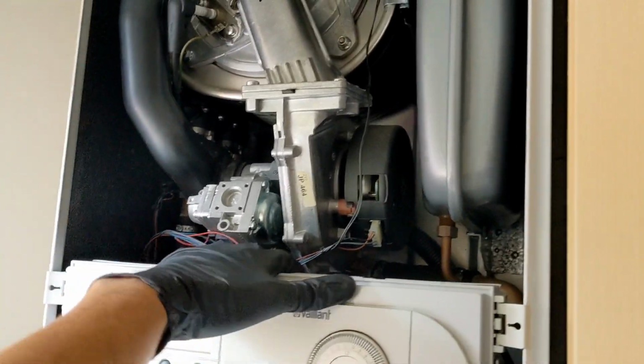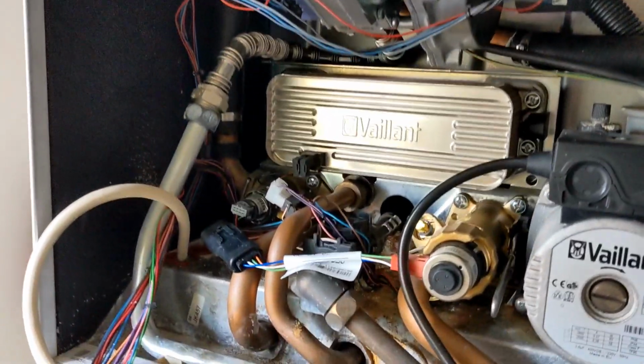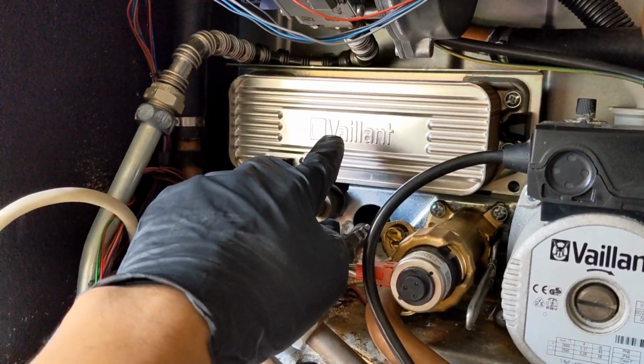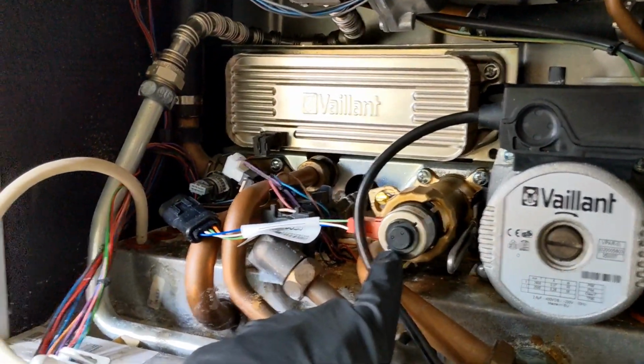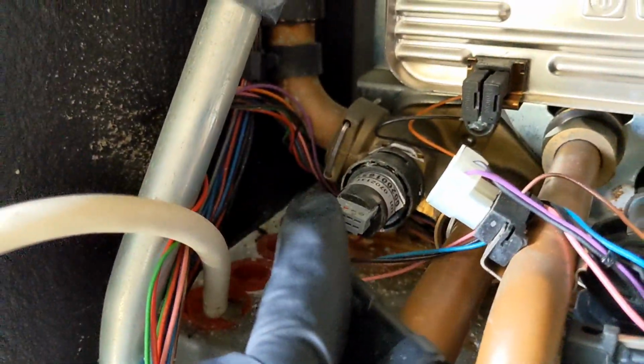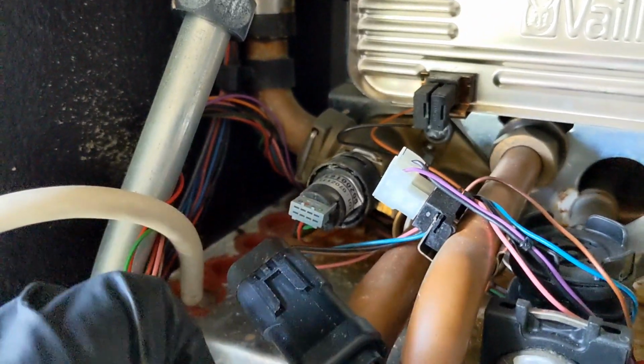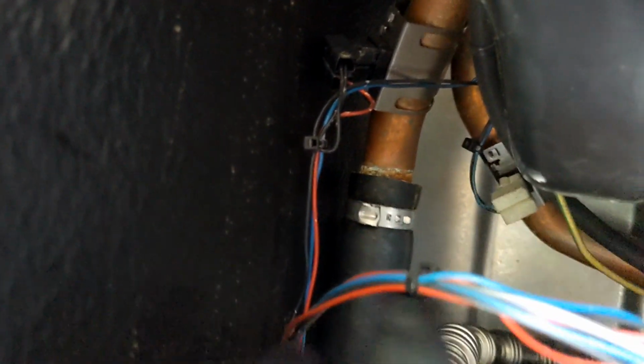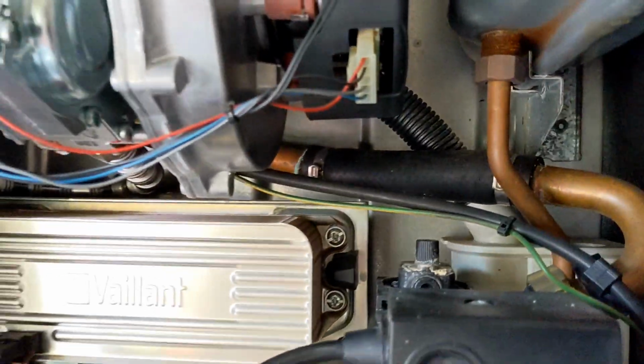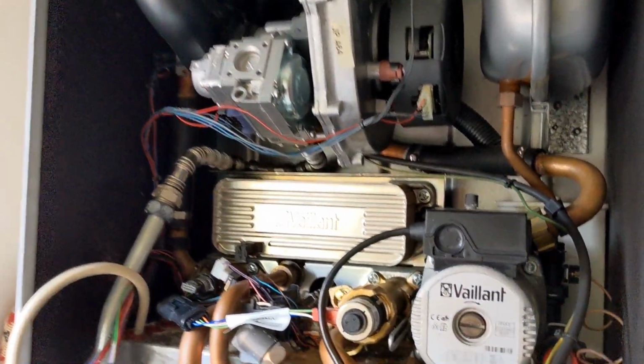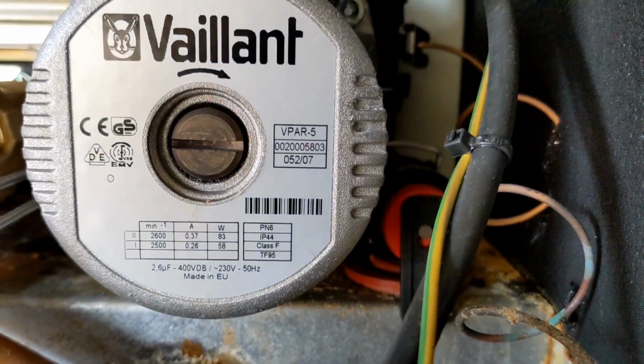Right, in today's job I'm going to be changing over the plate heat exchanger. It's already had a new diverter valve. I'm also going to be swapping over the pressure sensor, because that looks like the original one, upgrading the flow and return pipes from the hose connections to full copper ones, and swapping over the PRV as well.